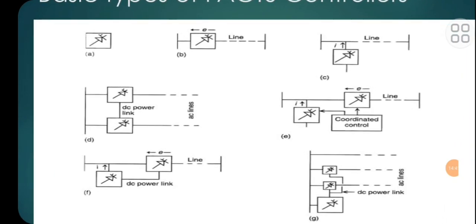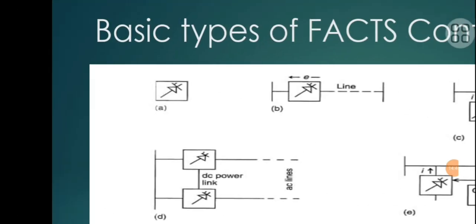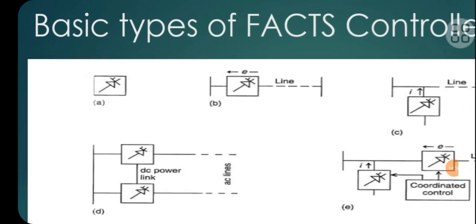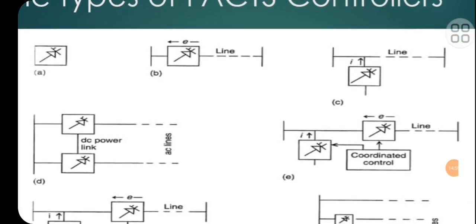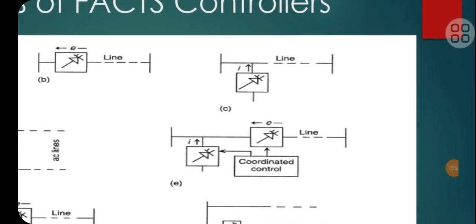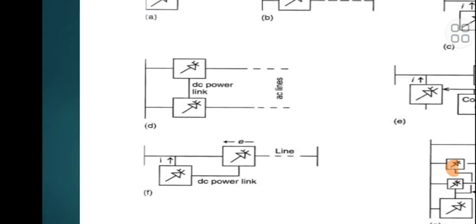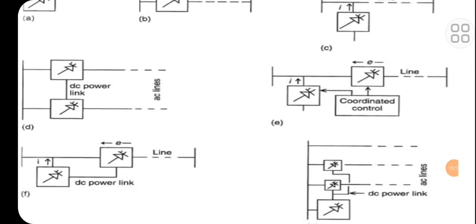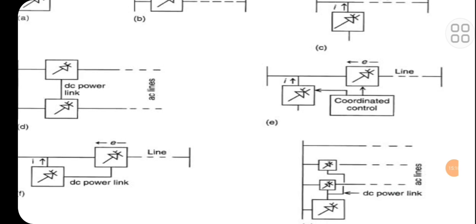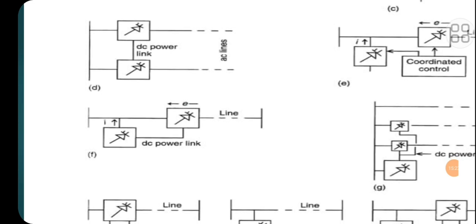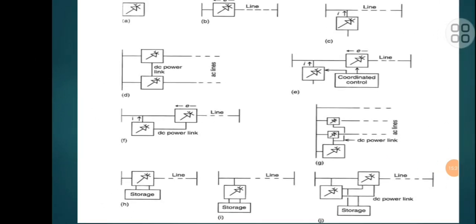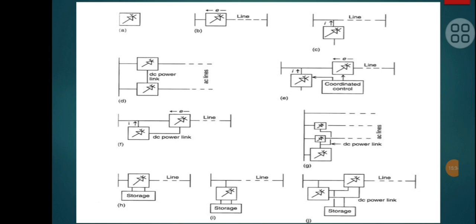These are the diagrams of various types of FACTS controllers. Figure A indicates the basic diagram, an illustration of the representation of a FACTS controller. A thyristor within a box indicates the symbol of a FACTS controller. Figure B is a series controller which is injecting a voltage E in series with the transmission line, and figure C shows a shunt controller injecting a current at the point of connection in the transmission line. Figure D is a combination of two series controllers. Then figure E is a combination of series and shunt controllers controlled in a coordinated manner. Figure F shows the combination of series and shunt control with a common DC power link. It is called UPFC. Similarly, G, H, I, J show various other types of FACTS controllers.